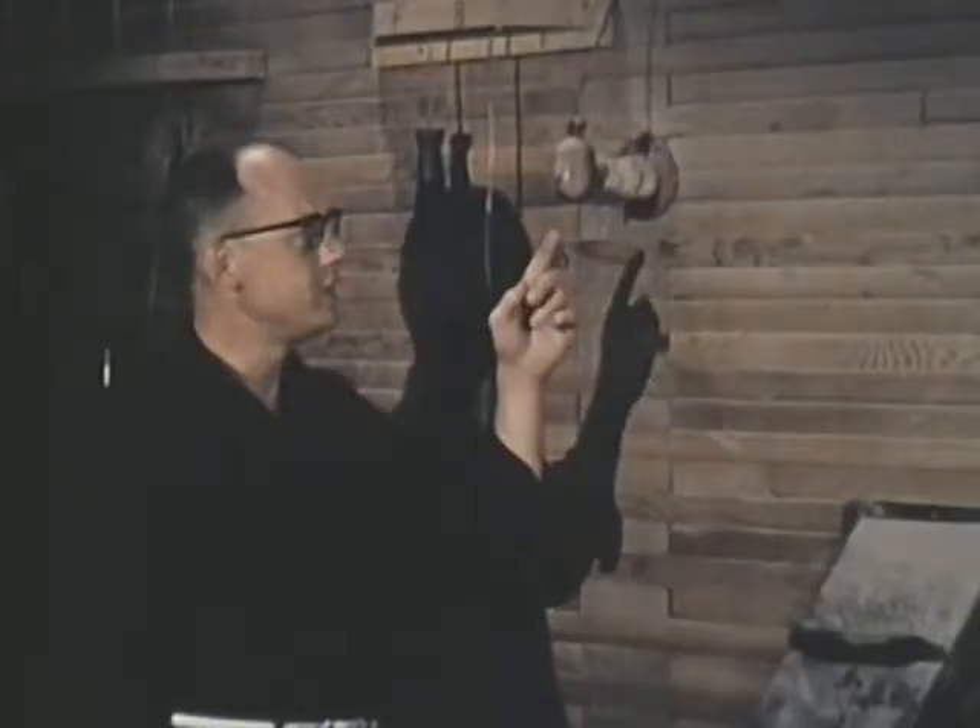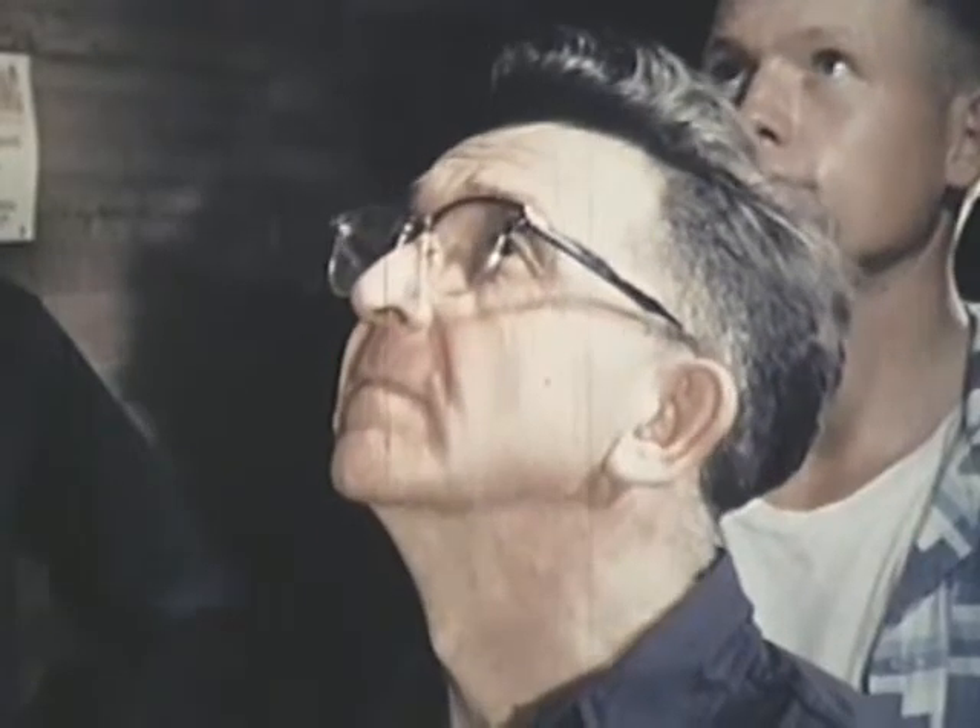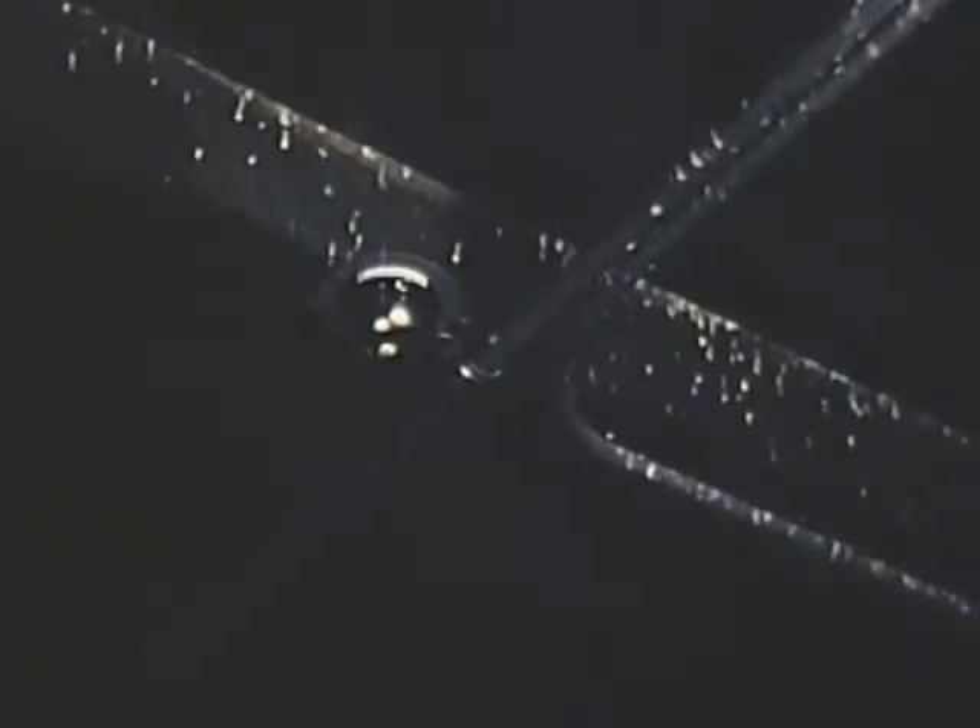This is one type of alarm system that has a wire running up and across the upper portions of the building. There are fusible links every few feet — when any of these reaches a certain temperature, it melts and activates the switch, which turns on the siren. Thermostats of this type are often used to supplement the fusible link arrangement, and on most new installations they are replacing the fusible links entirely. We need to make sure that all employees, the night watchmen, and people living in the area are familiar with the siren.